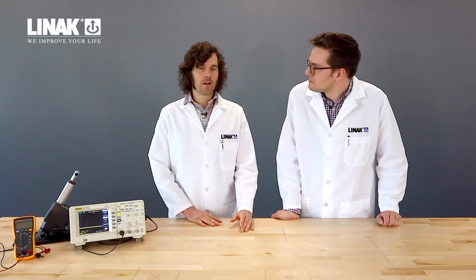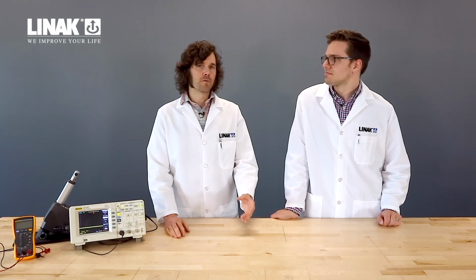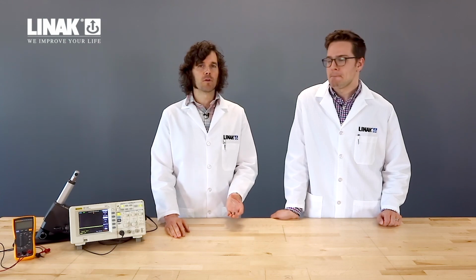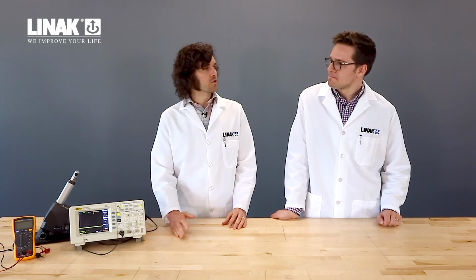So analog current, often 4 to 20 milliamps, is a very common type of feedback. It's less susceptible to noise and voltage drop over long cable runs, and most often used in PLC programming. Yeah, that's right. And that's all we have for feedback options.